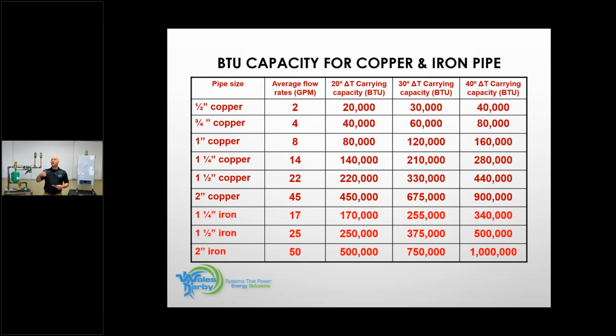And also on a 30 and 40 degree delta, most of the time it'll be a commercial type application on a 40 degree delta, but just take a look at the BTU that a 2-inch pipe can carry. I'll go with iron. So iron, 20 degree delta, I can carry 500,000 BTU comfortably. 40 degree delta, I can carry 1 million BTU comfortably in that pipe.